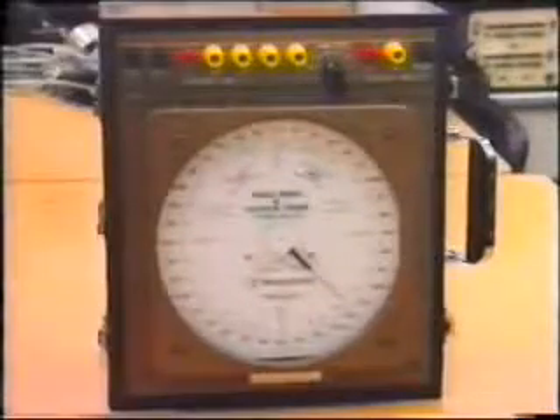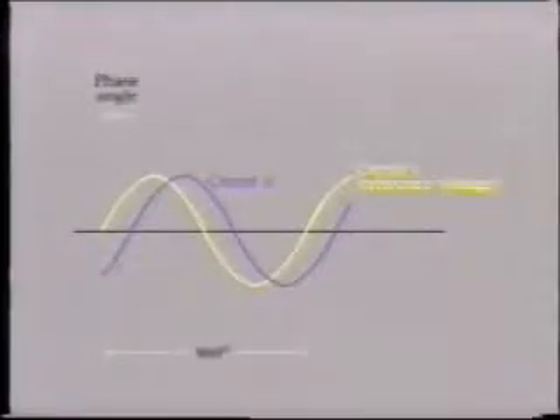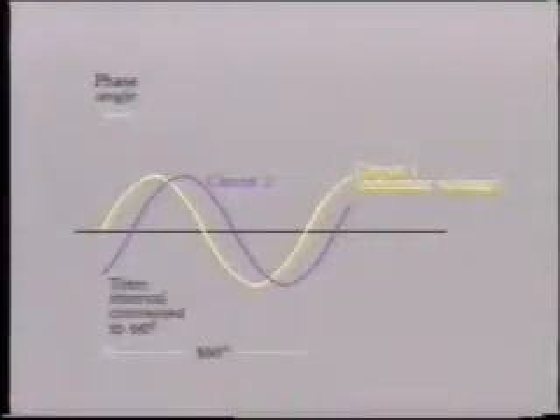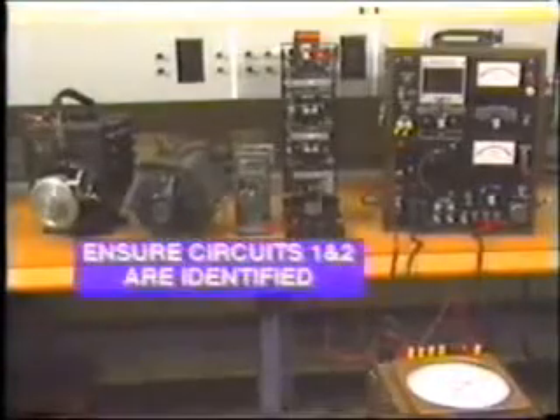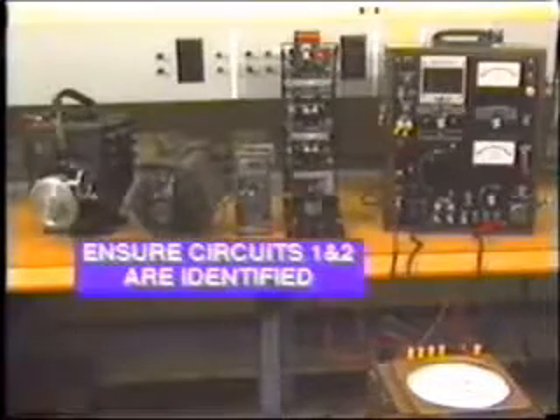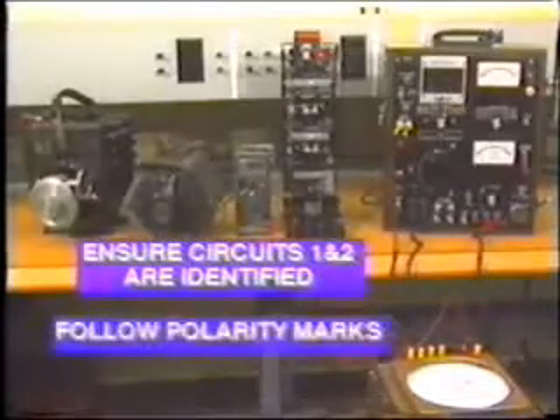All right, now let's turn our attention to measurement of phase angle. Correct phasing is essential for generator operation, relay directionality, and metering. Most phase angle meters work on the same principle, that is, to measure the time interval between the zero crossing of the two quantities. There are 360 degrees in one complete cycle, so the circuit is designed to convert the measured time difference into a phase angle reading. When using the instrument, great care must be taken to make sure that the circuits 1 and 2 are clearly identified, also that the polarity marks are followed.